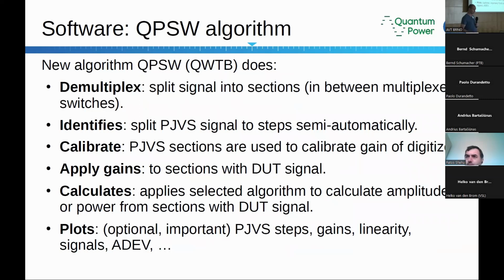So the algorithm that processes the data has to demultiplex, to split the measured signal into several sections between multiplexer switches. It has to find out in the Josephson signal what the steps of the Josephson are, and use these steps to calibrate the gain of the digitizer, then apply this calculated gain to the other sections with the signal we are measuring, and then calculate amplitude or power from the actual signal. The algorithm can also plot many features to show you if everything is working correctly.